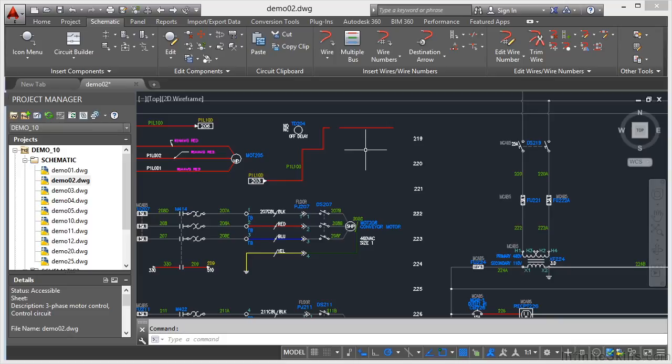That highlighted red because it was on an appropriate wire layer. When it wasn't on an appropriate wire layer, the SYMS layer, it just showed as a white line on that layer, and it stood out. You could see, because it wasn't highlighted in the red, you could see that it wasn't an appropriate wire for the wire network. So use that show wires command to find all of the wires that aren't connected or all of the lines that aren't actually wires in your AutoCAD electrical drawings.